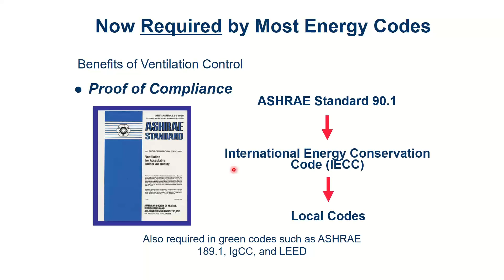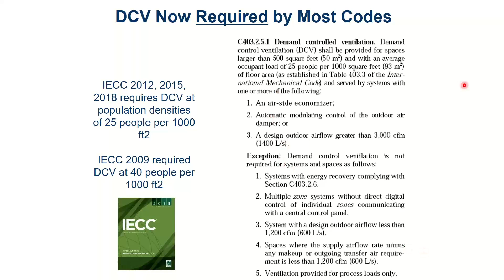What does that mean? Based on the code that we're using in Massachusetts, and for my coworkers sitting next to me here in Illinois, same code we use in Massachusetts and Illinois: anytime I have a space that's 25 people per 1,000 square foot ratio density—what does that mean? That means conference rooms, classrooms, restaurants, those kinds of places are going to have to do demand control ventilation. There are some exceptions for really small systems and for things that are not people-based, like a process load for a computer room or some weird things like that. But the normal spaces, I'm going to have to do that.